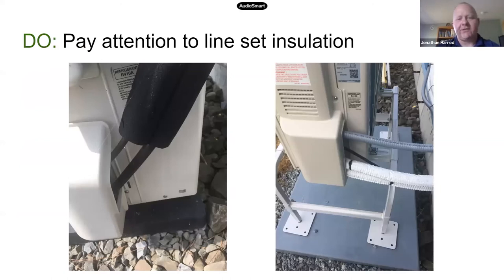Line set insulation. The copper tubes are called line sets. We've just expended a bunch of energy to extract heat from the cold outdoor air. We don't want to lose that heat back to the outdoor air by having lousy insulation like you see here on the left. We want to make sure that insulation is done really thoroughly, all the way from the outdoor unit to the indoor units. In air conditioning, if we have bad line set insulation, we can get other problems. We can get condensation inside walls and other things that can cause a lot of headaches.